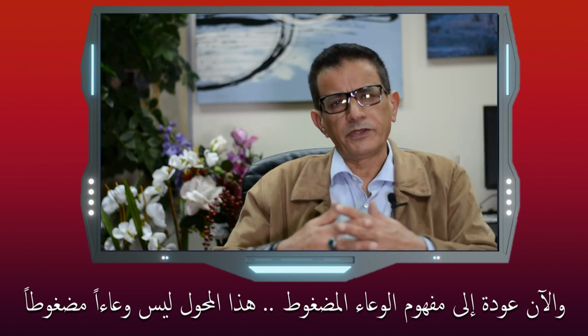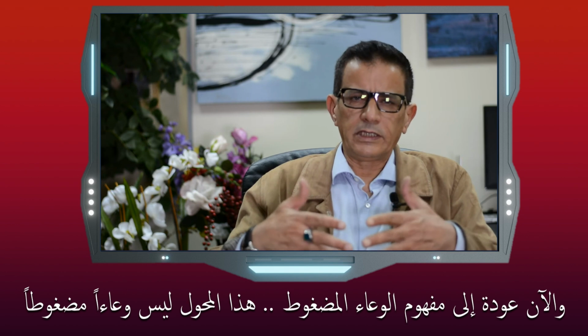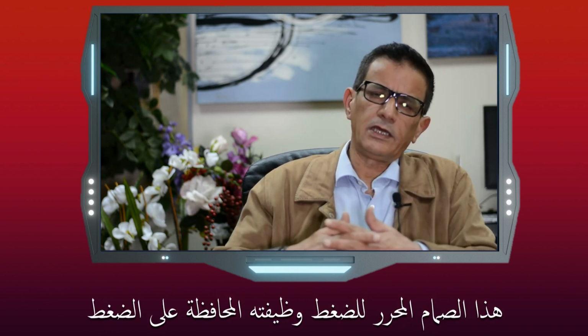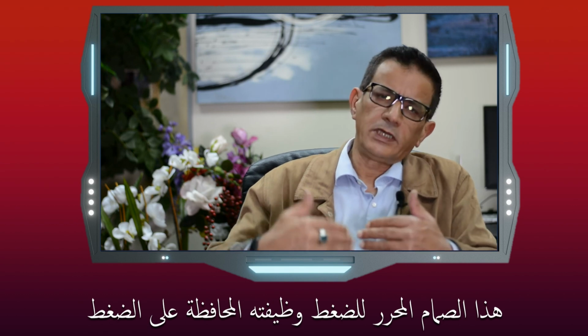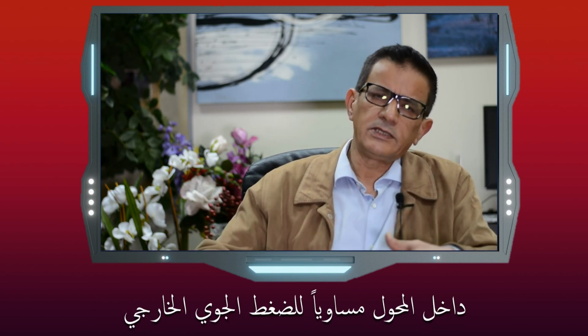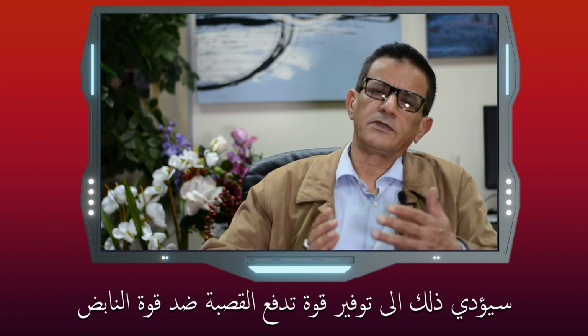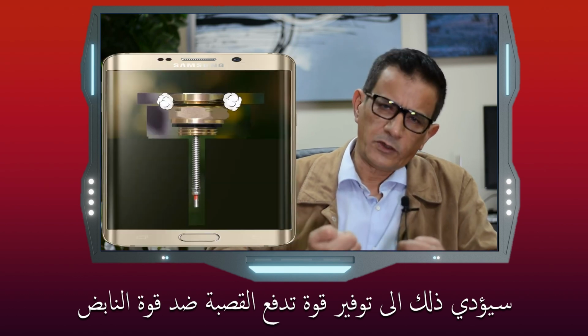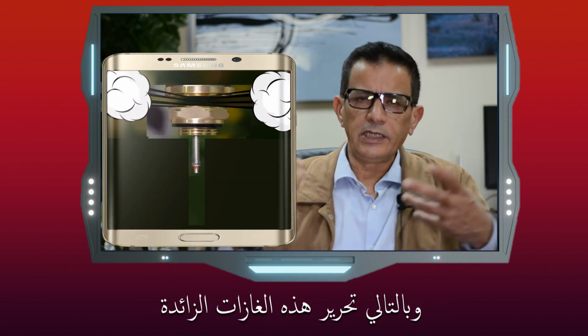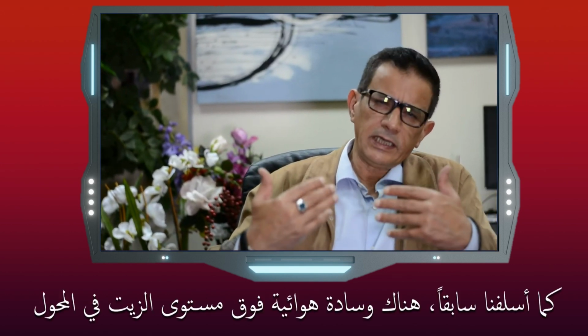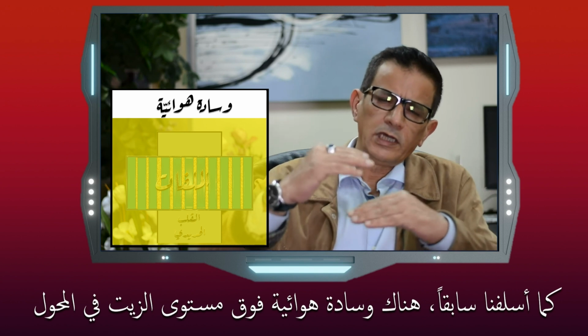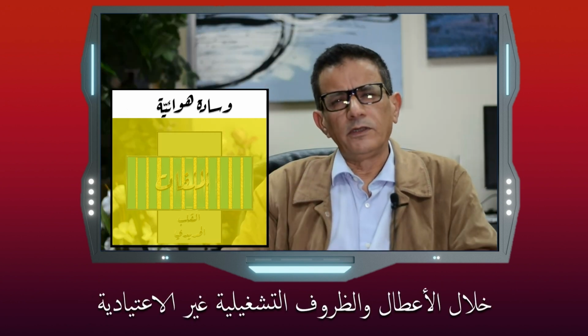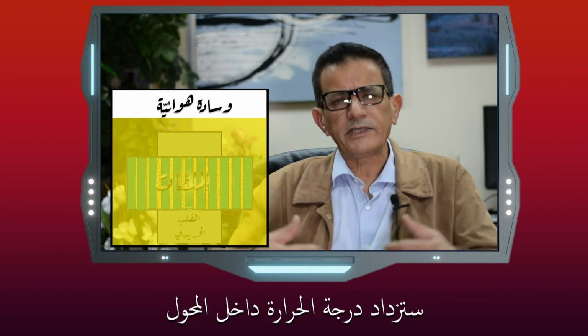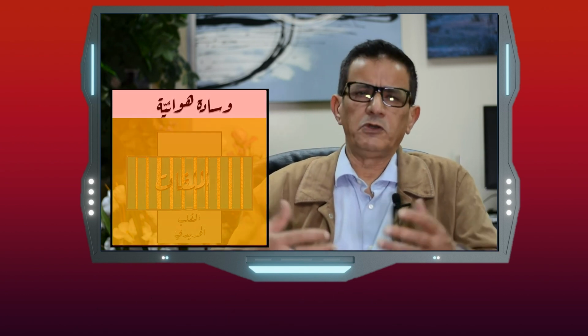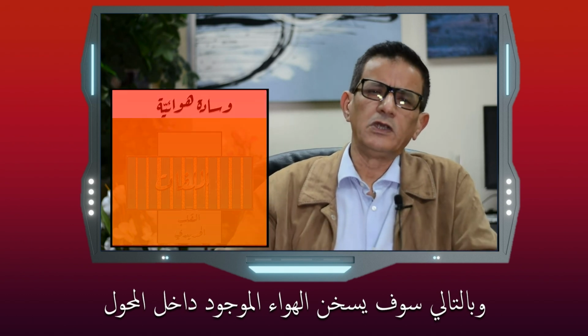So back to the pressurized vessel concept. This transformer is not a pressurized vessel. This PRV, pressure relief valve, is to maintain the pressure inside the transformer the same as the outside atmospheric pressure. Whenever there is an excess pressure inside the tank, this will provide a force which will move the rod against the spring force, and will release these extra gases. As we explained earlier, there is an air cushion above the oil level in the transformer. During faults and abnormal conditions, extra heat is generated inside the transformer. So this air, this gas inside the transformer, will get heated.